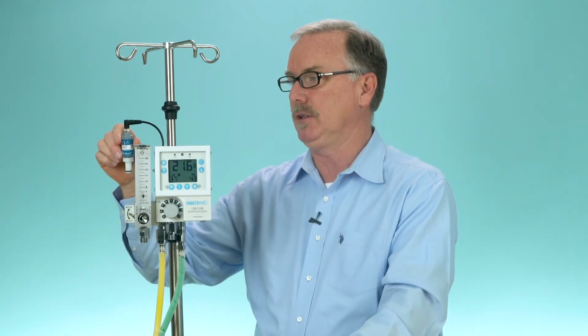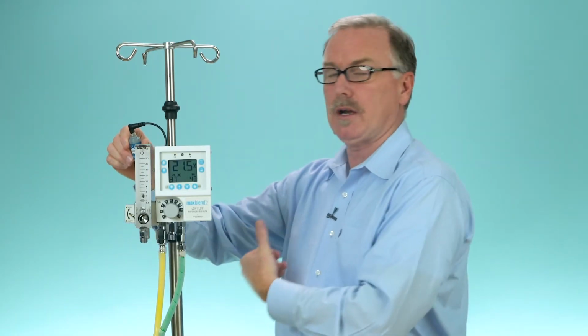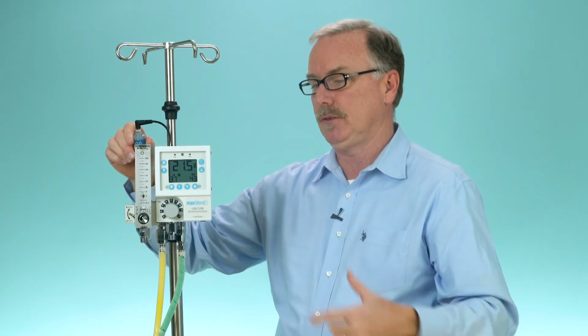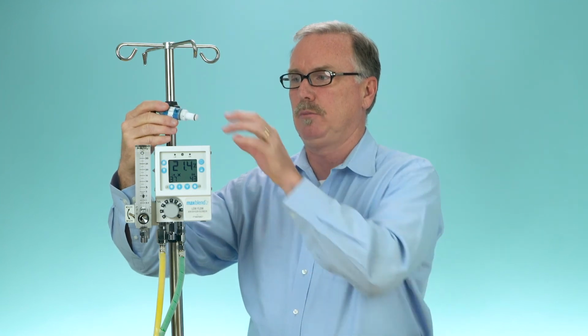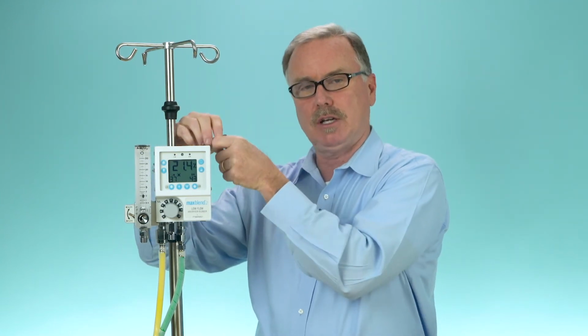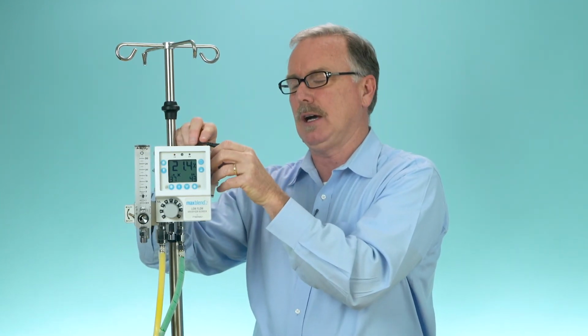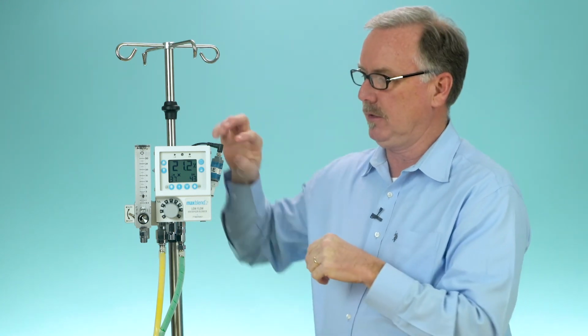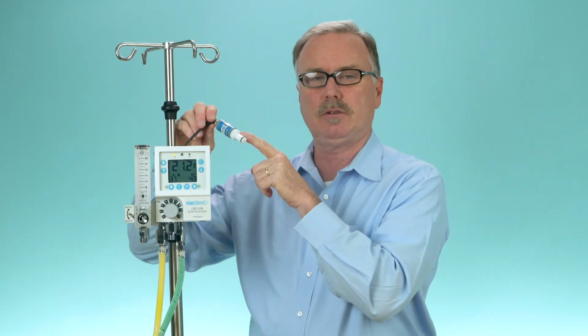The same thing could be done in room air. If you have a room air flow meter and it's readily available, take the fuel cell out of a MaxBlend 2, put it into that room air environment, flush it. Now you can also use, maybe not a glove, but a piece of flex tube with a T-piece. I'm sure the therapists out there know what I'm talking about. The key is to flush that area that this sensor tip is being exposed to.